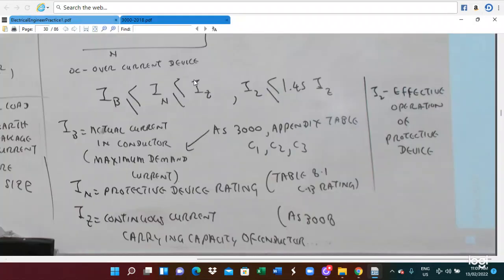IZ means the continuous current carrying capacity. Where the electrical current is drawn by the supply system, we have to select the appropriate continuous current rating by using AS3008. So this is the configuration. IB must be less than or equal to IN, which must be less than or equal to IZ. This means the actual current must be less than or equal to the protective device rating, and the protective device rating must be less than or equal to the continuous current carrying capacity. So this is the way we have to arrange the supply wire.